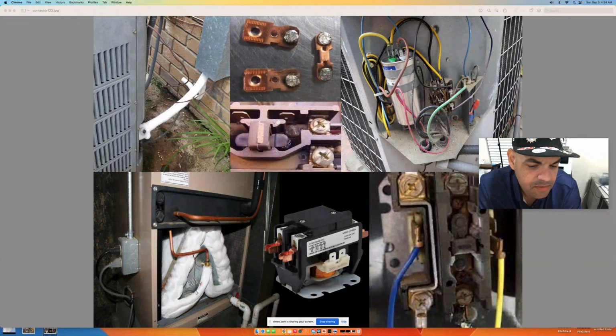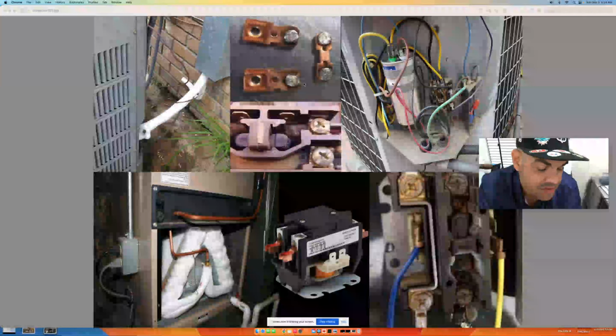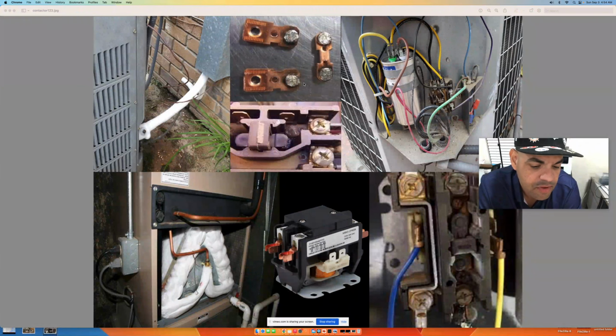When the contacts go bad, if you look at the top here where I'm using my mouse, sometimes these contacts can go so bad that they just won't send any voltage to the other side. So it'll get stuck and look like it's pressed down, but you're not going to get any voltage going to your actual outdoor AC unit. You can use a multimeter. Another way you can check if there's a loss of voltage to the other side is you get a meter and check if there's voltage on one side, and if there's no voltage on the other side, then you know your contactor is no good. That's one way to troubleshoot it.